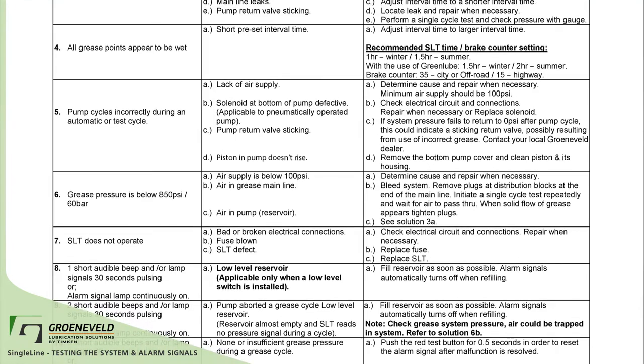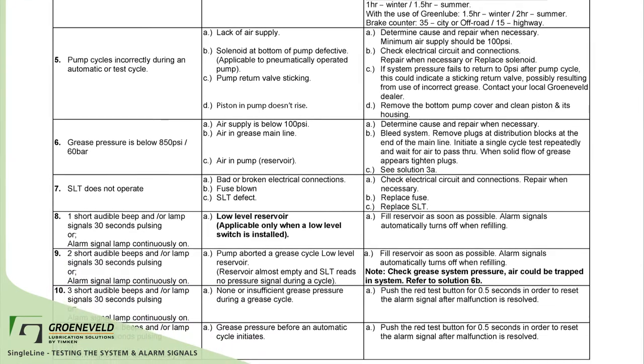Common things that can cause faults: air in the Greenlube grease, mainline leak, lack of pressure. For a full list of faults and causes, refer to the SingleLine system troubleshooting chart.